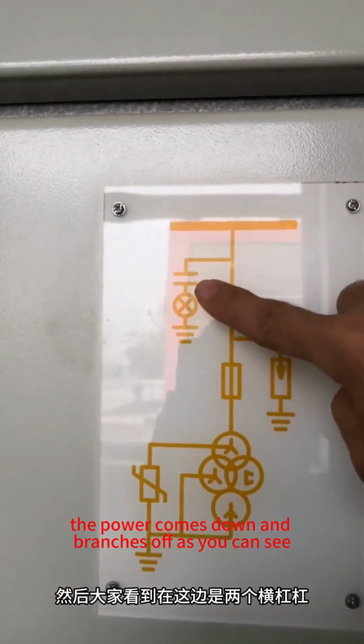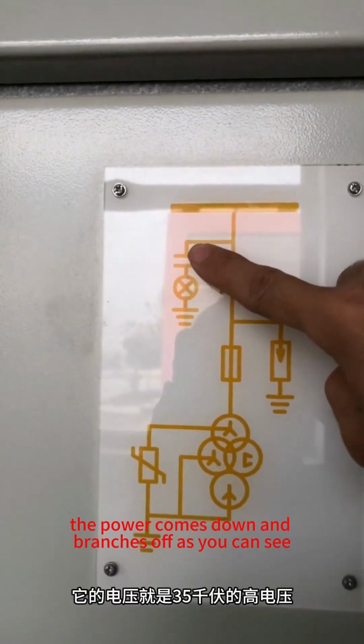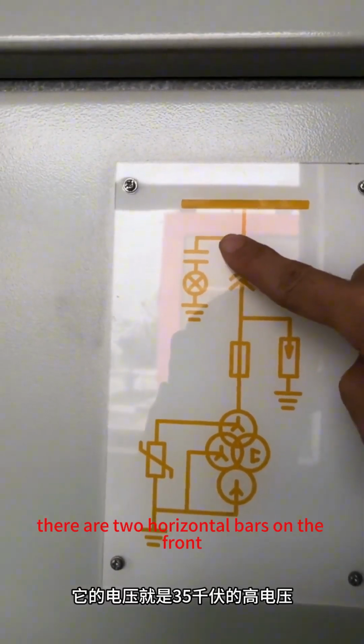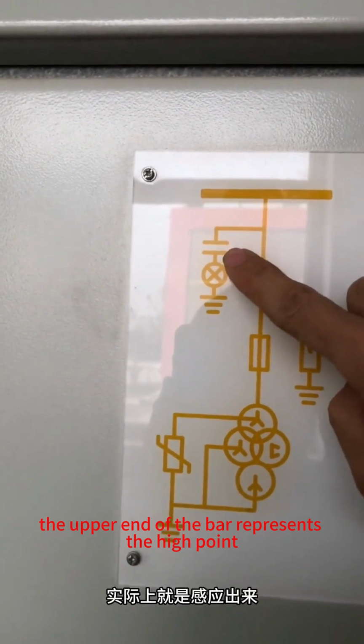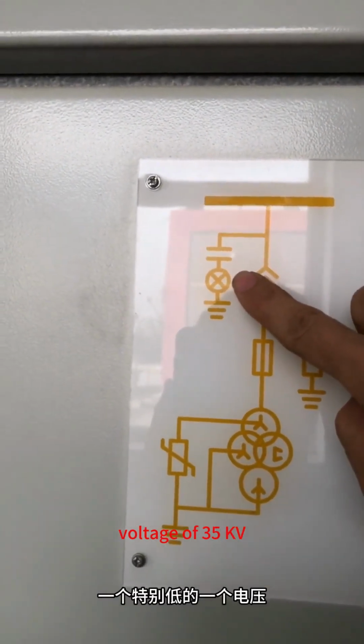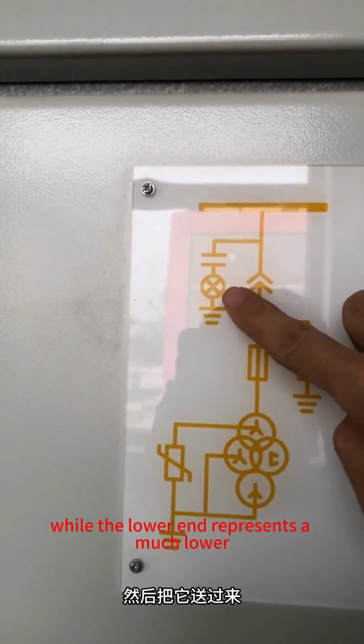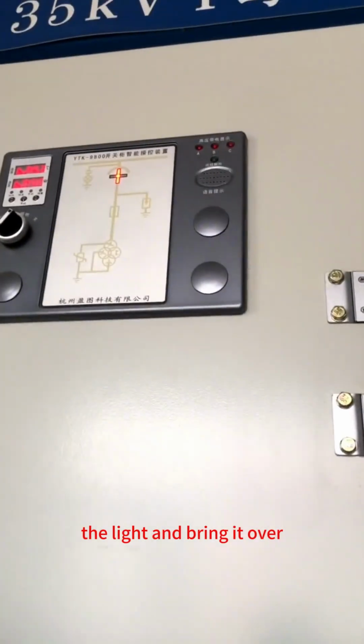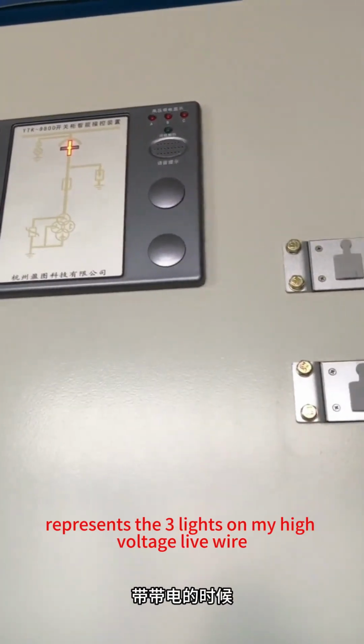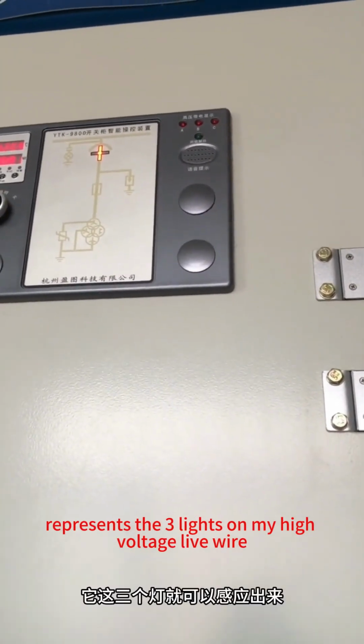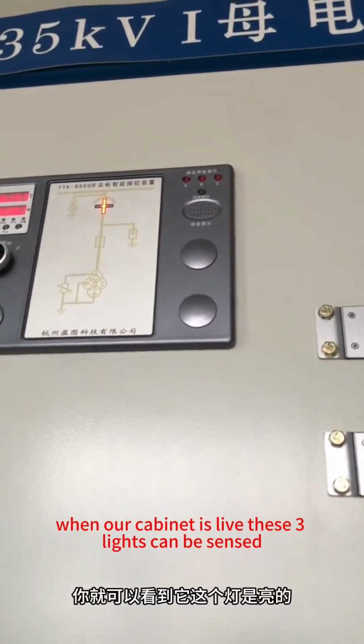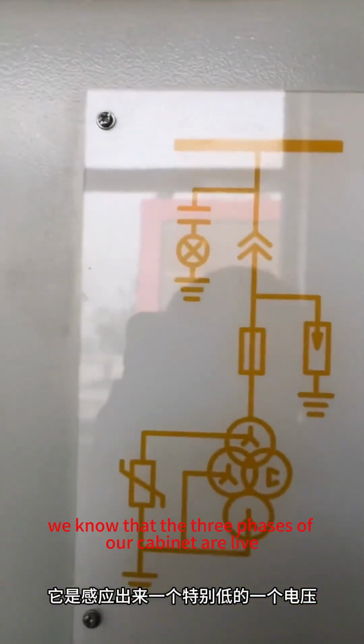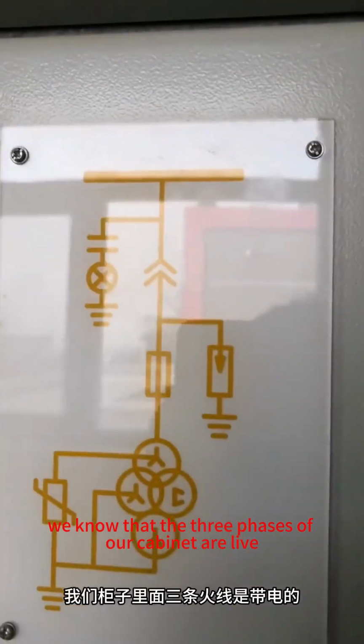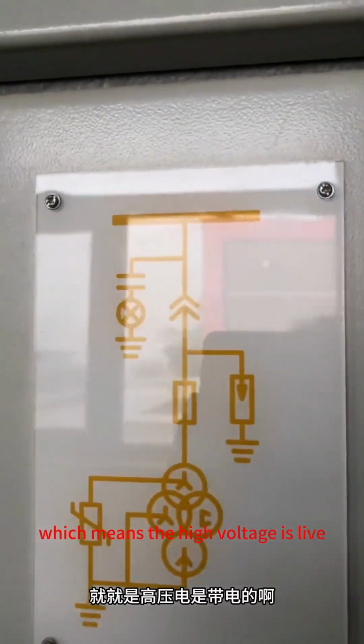The power comes down and branches off. As you can see, there are two horizontal bars at the front. The upper end of the bar represents the high voltage of 35 kV, while the lower end represents a much lower induced voltage that powers the light. The lights you see represent the three indicator lights on my high voltage live wire. When our cabinet is live, these three lights sense it, and when they light up, we know that the three phases of our cabinet are live, which means the high voltage is live.